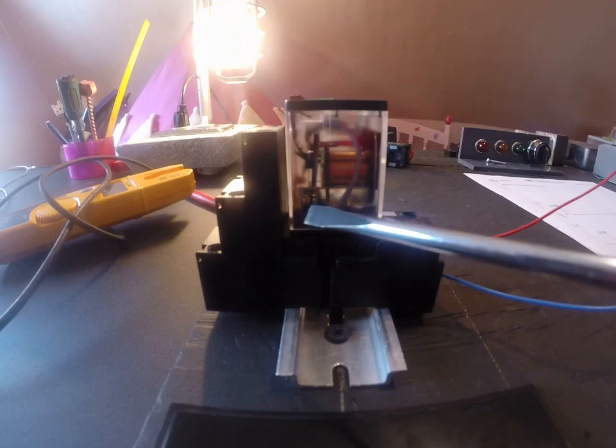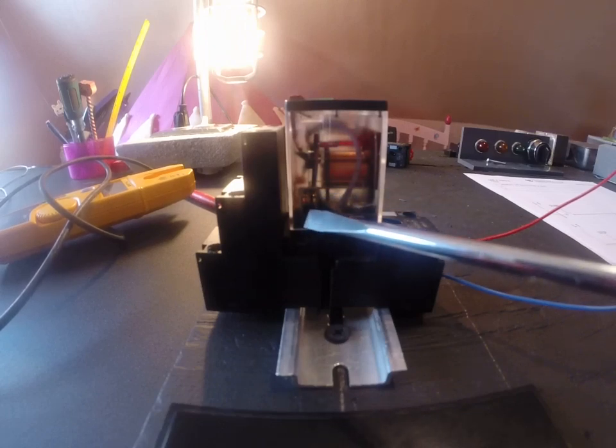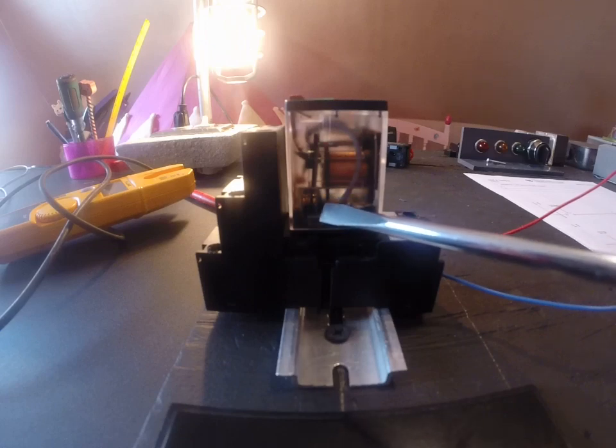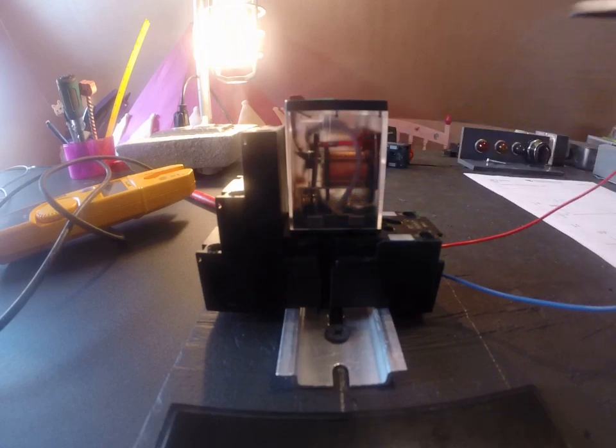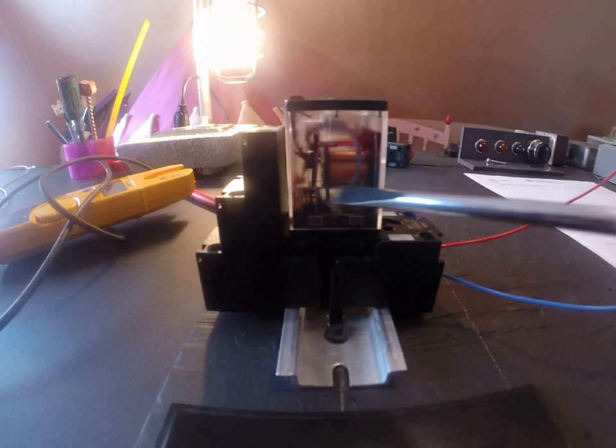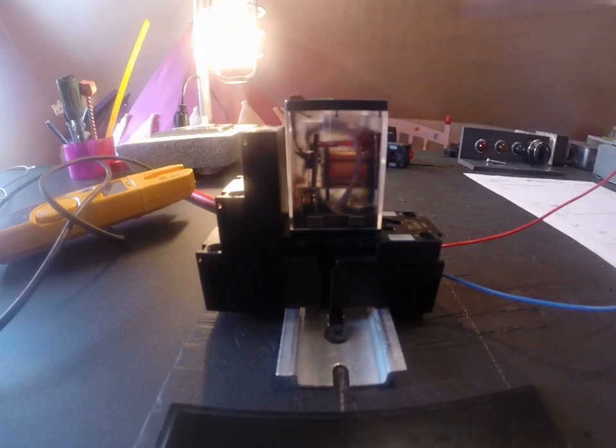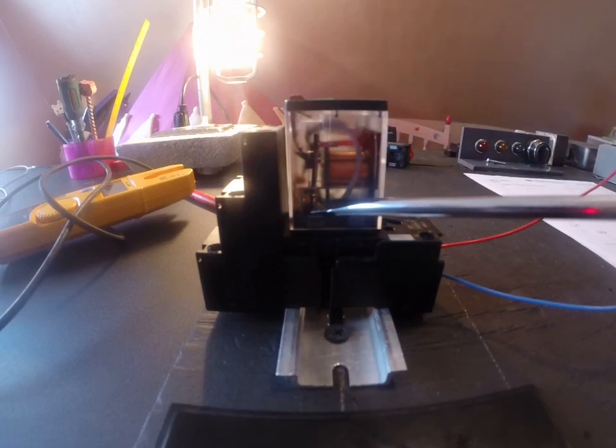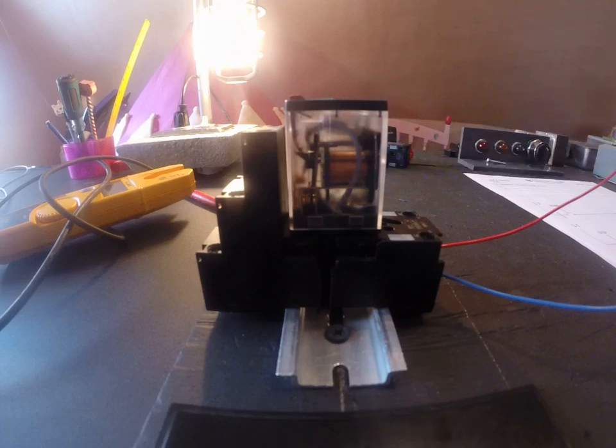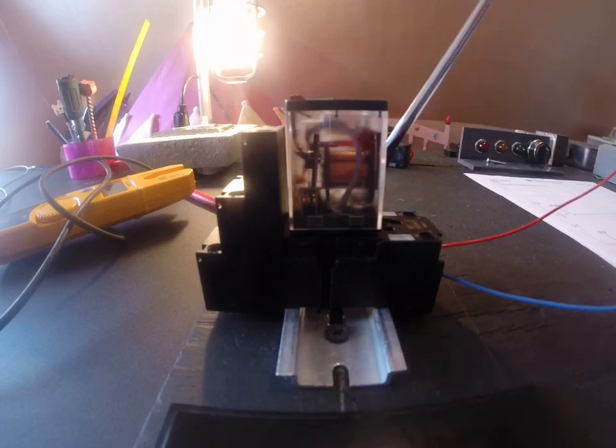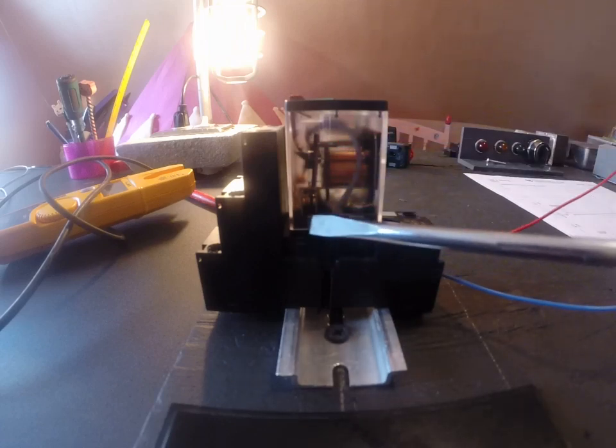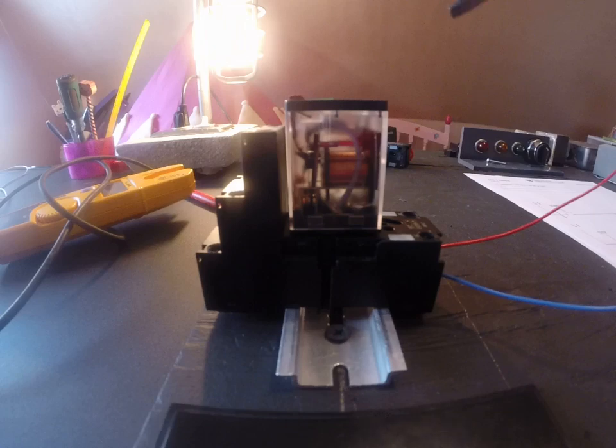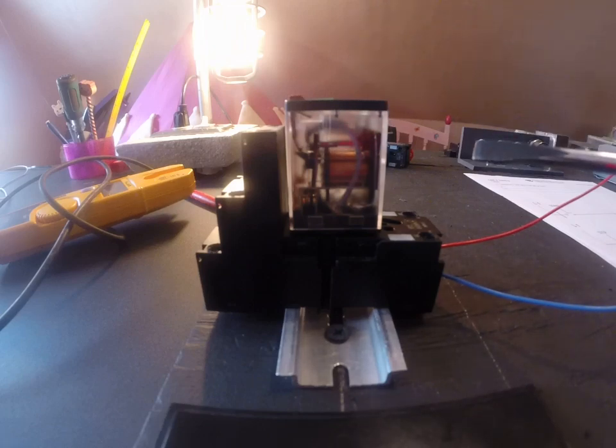And when I do that it changes the position of these contacts that are underneath. Now these contacts that are underneath we refer to them as normally open, normally closed and common. And each relay has at least two sets of those contacts. One on one side and one on the other. It's got a set of normally open and normally closed here and on the other side, it's got the same thing.